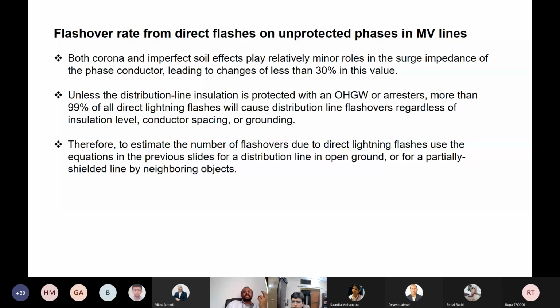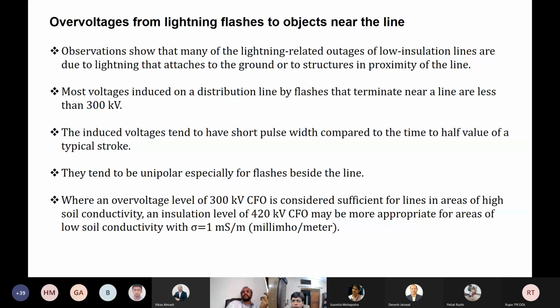Then overvoltages from lightning flashes to objects near the line. This is another important thing. Observations show that many of the lightning related outages of low insulation lines are due to lightning that attaches to ground or to structures in proximity of the line. I'm sure that many of you know that. Then most voltages induced on distribution lines by flashes that terminate near a line are less than about 300 kilovolts. I will show you the equation to calculate that later. So usually these values are less than 300 kilovolts.